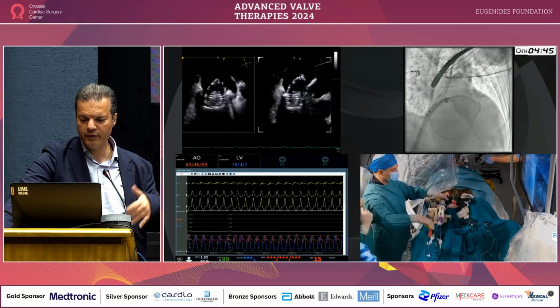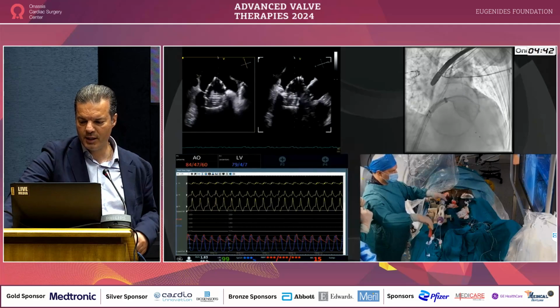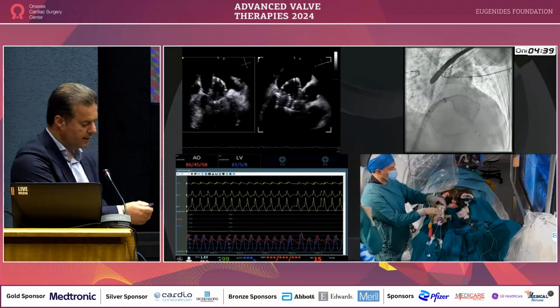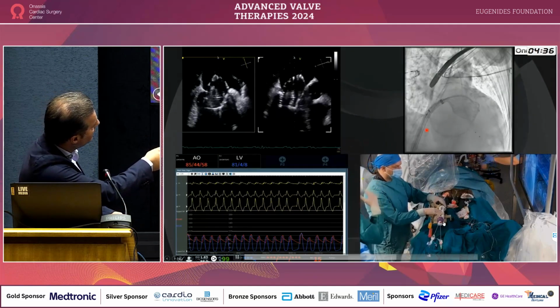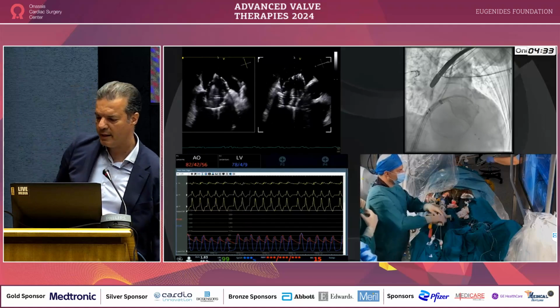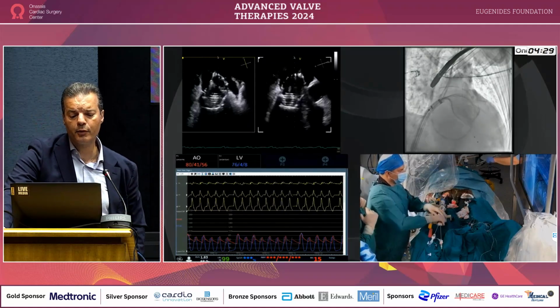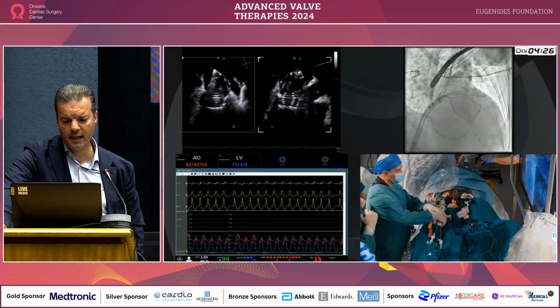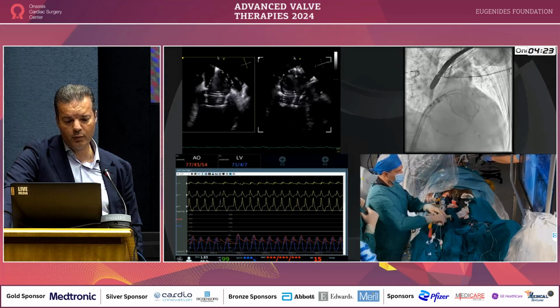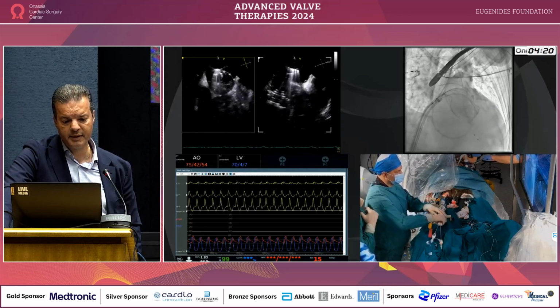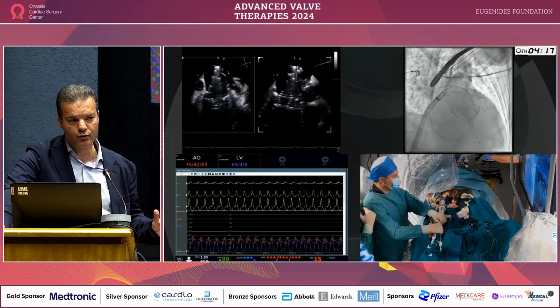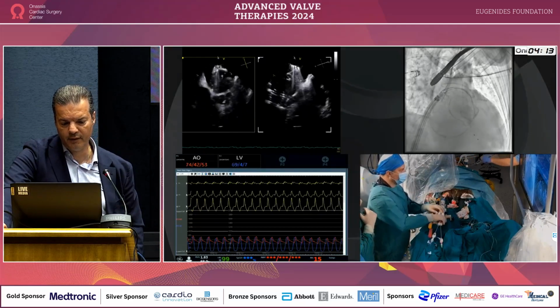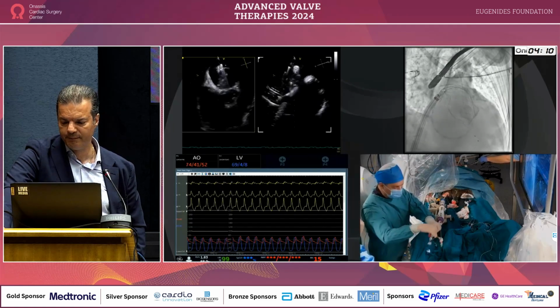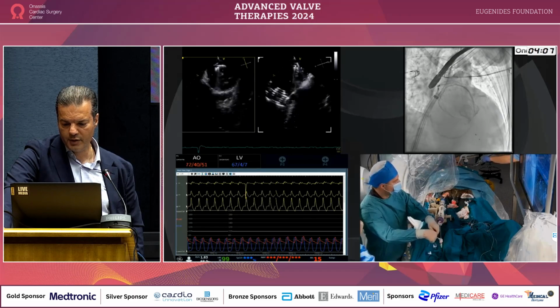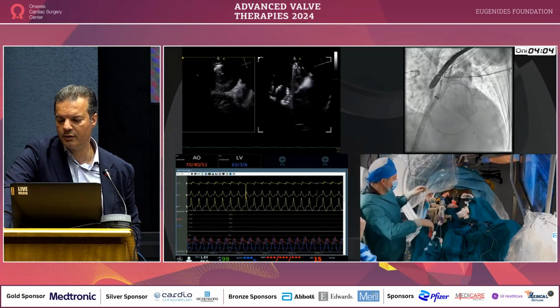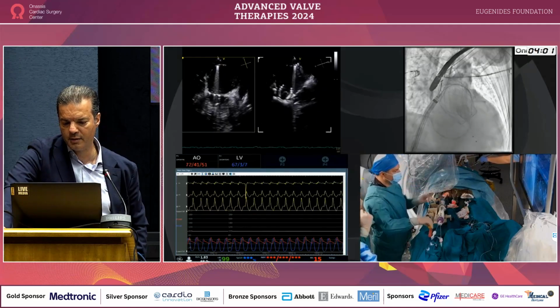By removing the inner catheter and the outer catheter and adjusting the positioner, which is this little 6-French catheter in the middle of the assembly going down to the valve, you're just able to deploy your valve. You can see the progression of this deployment on the echo. You can see the cage opening and filling up the left atrium. And actually what we have found is that once you open about 60% of the cage and you engage on the lateral wall and the atrial septum, the valve remains very stable. So we reach to the top, we push the insertion catheter to the rooftop of the left atrium, and now the cage is fully deployed.